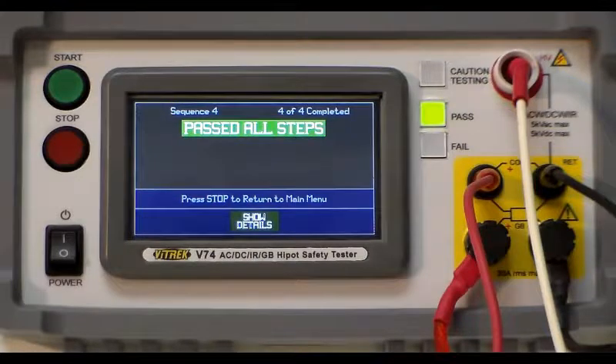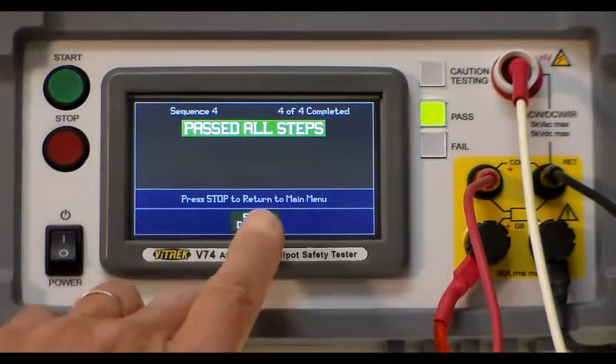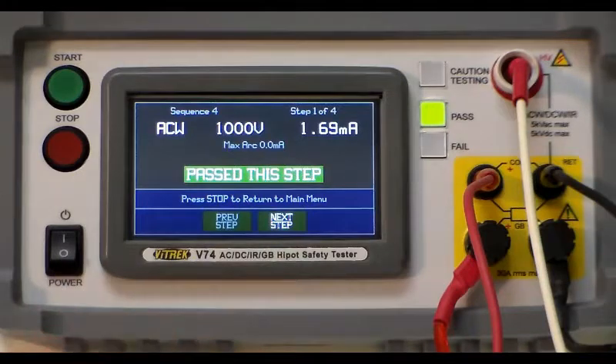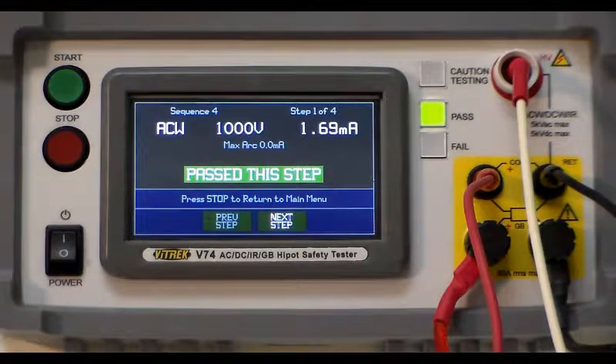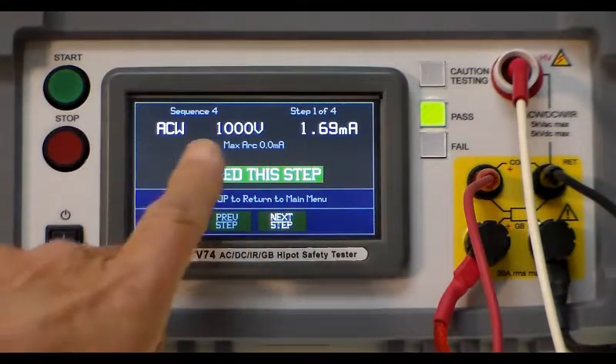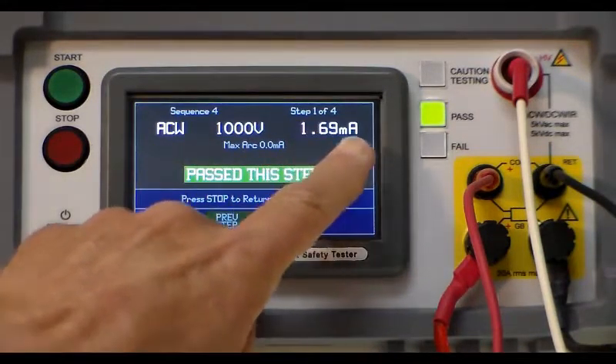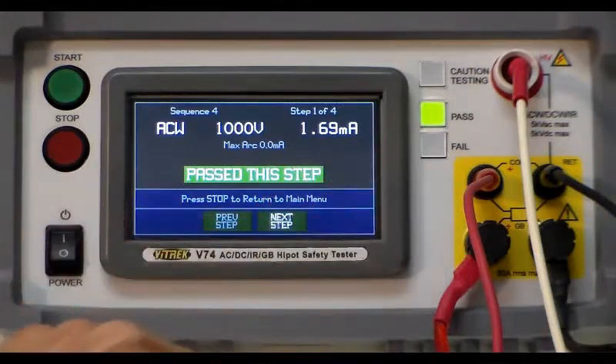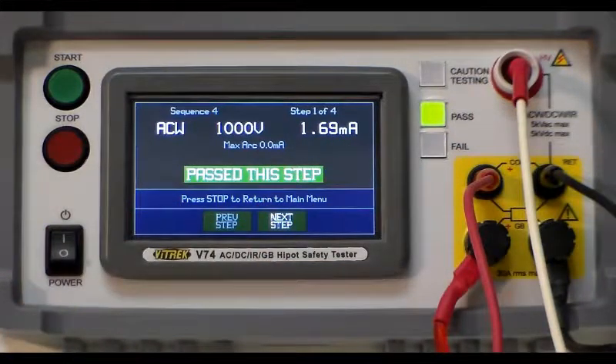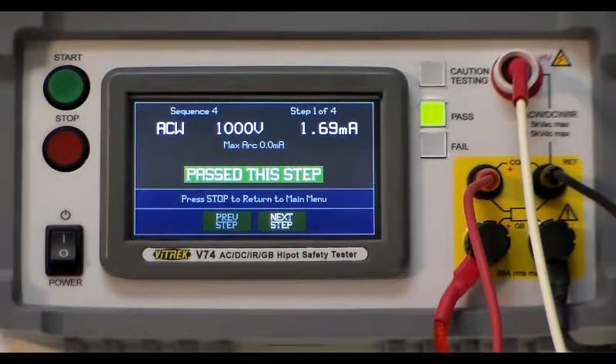Once you get to the end of the test there's an option to show the details. And what that will do is it'll show you the results of your test. In this case the ACW was 1.69 milliamps. I happen to know there's a transformer in this particular unit which gives a bit of a reading.